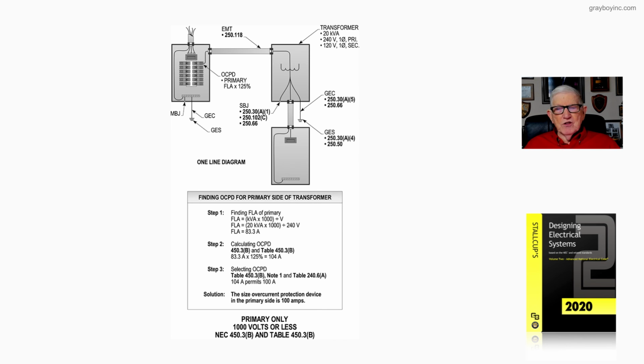So this figure 20-10 just basically shows the procedure for sizing the primary overcurrent device only. You're protecting the primary at 125%. It's a 1,000 volts or less rated transformer. And we're following the requirements of 450.3(B) and Table 450.3(B). And that's what our figure 20-10 is illustrating. The transformer has a primary current of 9 amps or more, and we're using the 125% times that primary current of 83.3, and we can either round it up to the next size protective device or round it down to the next size protective device listed in our Table 240.6(A) in the NEC.